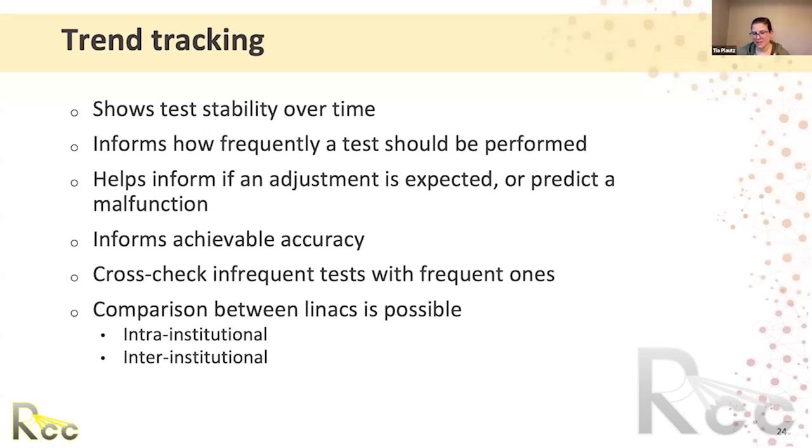So again, with the couch example, if you've been testing your absolute positional accuracy every month for 2 years and it's never failed, and you don't ever use the absolute couch position, you only ever care about relative couch position, then it probably is perfectly safe to reduce the frequency of that test because you're not really even using that information in your day-to-day practice.